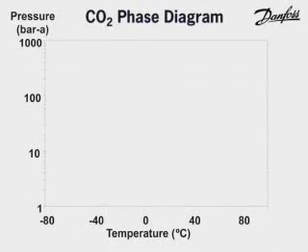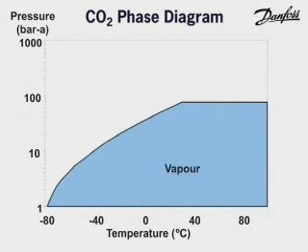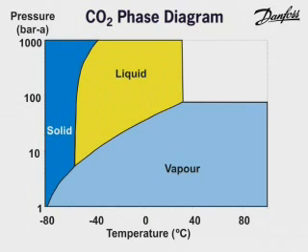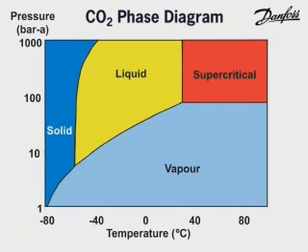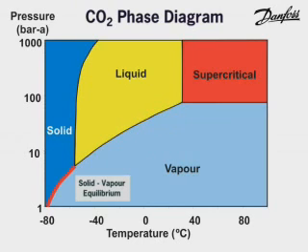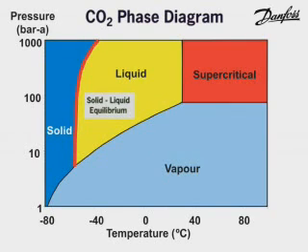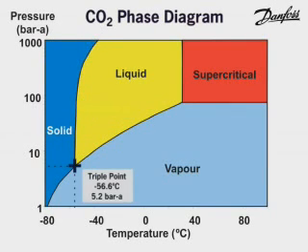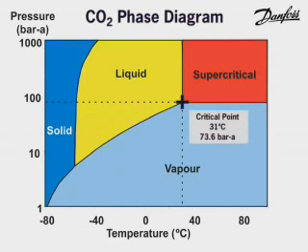In this diagram, the coloured areas define the temperature and pressure limits at which the CO2 vapour, liquid, solid and supercritical phases exist. This is known as the temperature-pressure diagram or phase diagram for pure CO2. The red solid lines indicate the pressure and corresponding temperatures at which two different phases of CO2 exist in equilibrium — for example, liquid and vapour, solid and vapour, and solid and liquid. Here is the triple point and here is the critical point on the phase diagram.